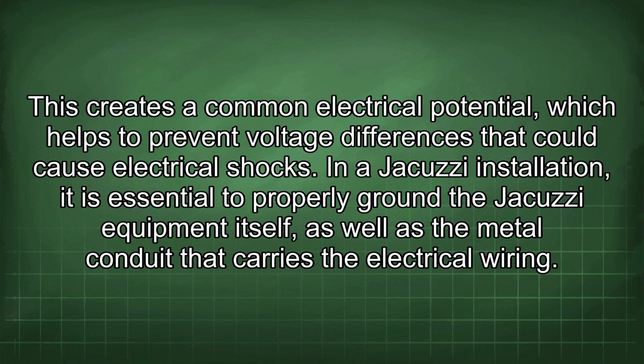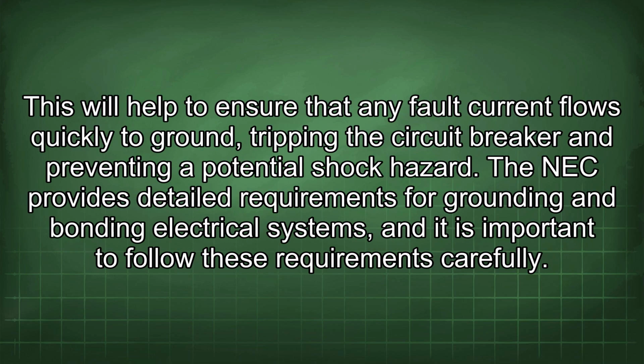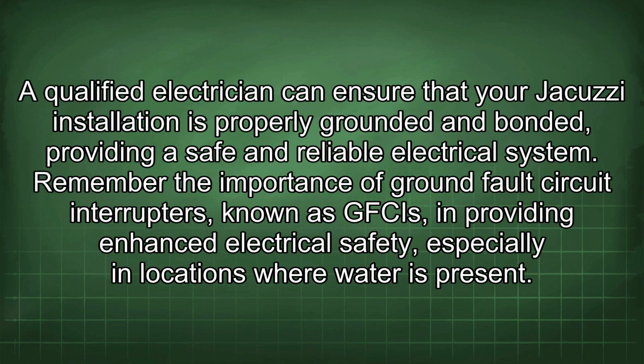In a jacuzzi installation, it is essential to properly ground the jacuzzi equipment itself, as well as the metal conduit that carries the electrical wiring. This will help to ensure that any fault current flows quickly to ground, tripping the circuit breaker and preventing a potential shock hazard. The NEC provides detailed requirements for grounding and bonding electrical systems, and it is important to follow these requirements carefully. A qualified electrician can ensure that your jacuzzi installation is properly grounded and bonded, providing a safe and reliable electrical system.